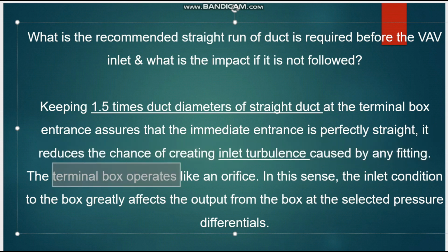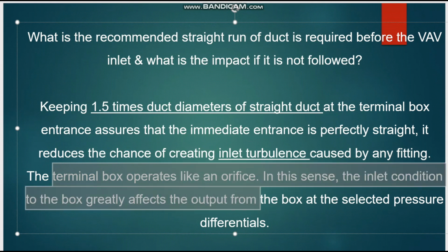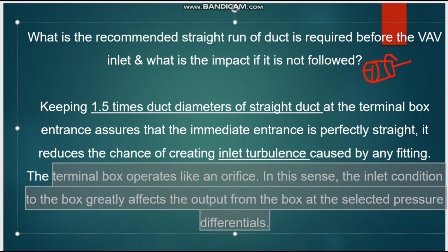And the terminal box operates like an orifice. So in this sense, the inlet condition to the box greatly affects the output from the box at the selected pressure differential. So normally in the VAV, what happens? In the VAV we have two pressure sensors, flow sensors, one at the inlet, one at the outlet. At the inlet it will measure the total pressure, and at the outlet it will measure the static pressure. So the difference of these two makes the differential pressure. Based on the differential pressure it will control the flow. So this differential pressure is very important in the VAV. So we have to avoid inlet fittings before the entrance, so we can make the proper selection of differential pressure in the system.